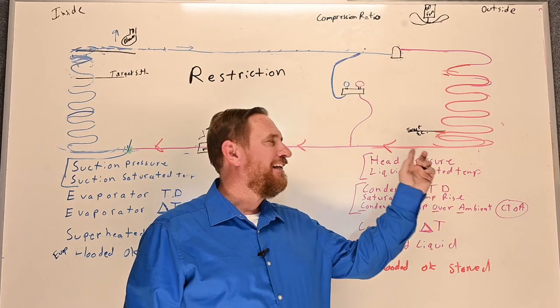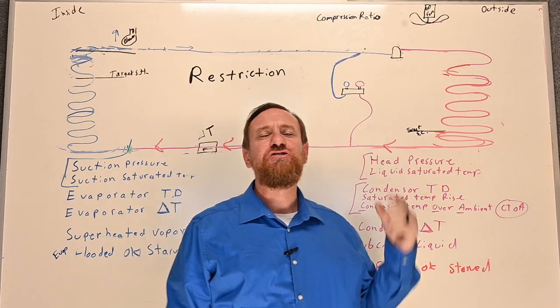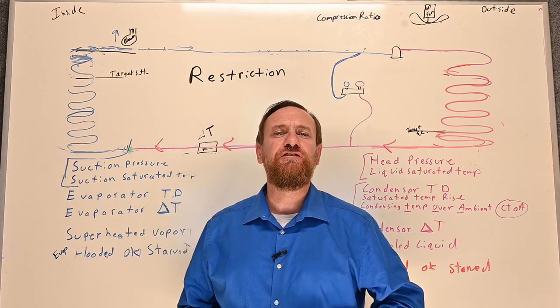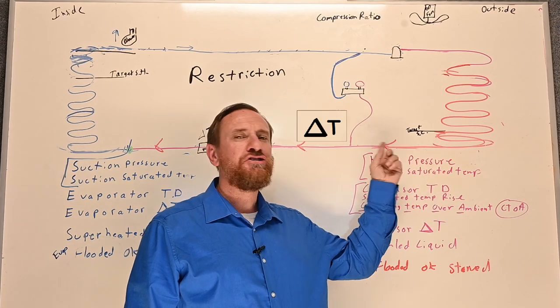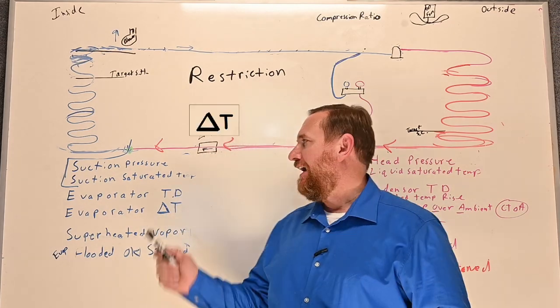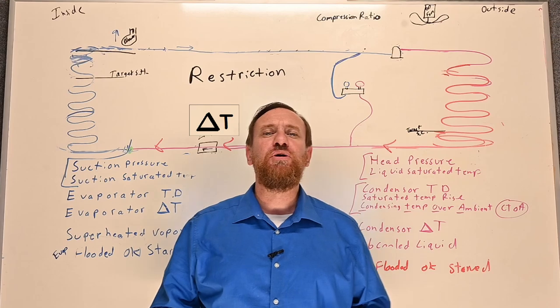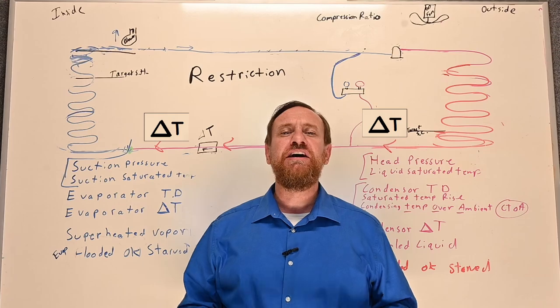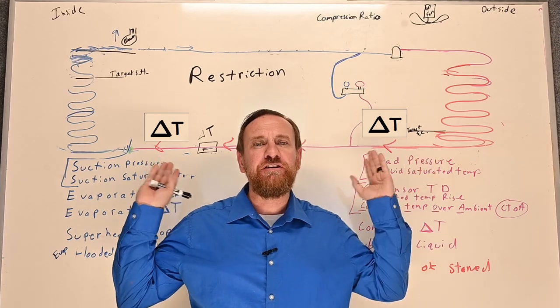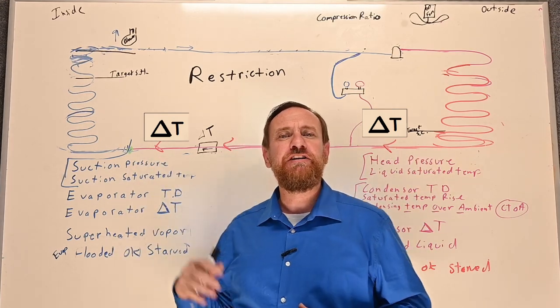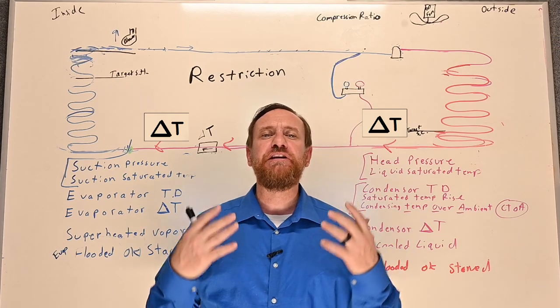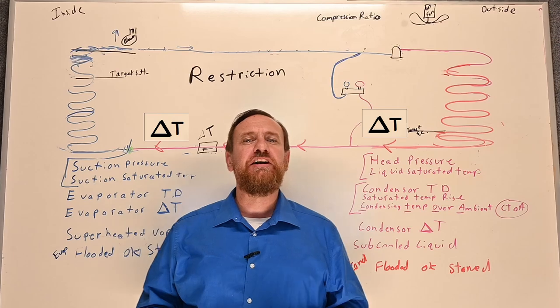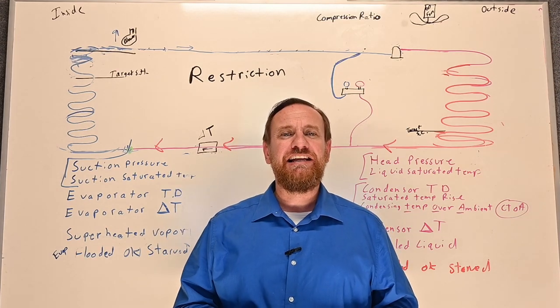What about a liquid line service valve? If there's a restriction there, maybe somebody didn't open it all the way — we can take the cap off and see if it's fully open. We can also check temperature drops across multiple locations. I once found a restriction in a liquid line through a wall by checking the refrigerant temperature going into the wall versus coming out, and found a big temperature difference, which also indicated a pressure drop. We cut the wall open and found a carpenter had kinked the line.